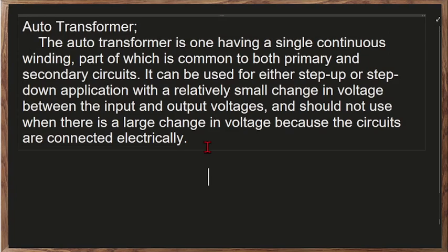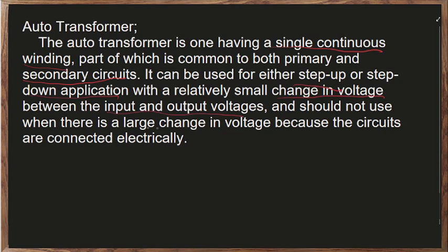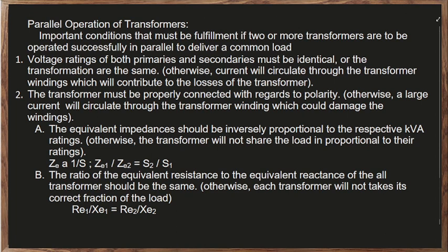And we have here a special type of transformer, which is an autotransformer. This is the only transformer that has a single continuous winding, no? So it has only one winding, which is continuous, part of which is common to both primary and secondary. It can be used for either step up or step down applications with a relatively small change in voltage between input and output voltages, and should not be used where there is a large change in voltages because the circuits are connected electrically. So if the step up or step down difference is small, we could use the autotransformer.